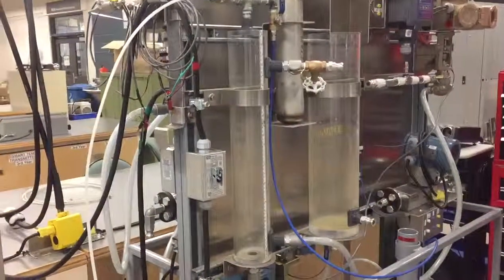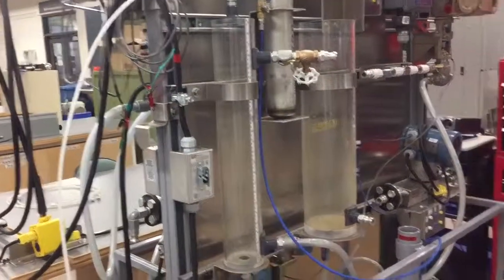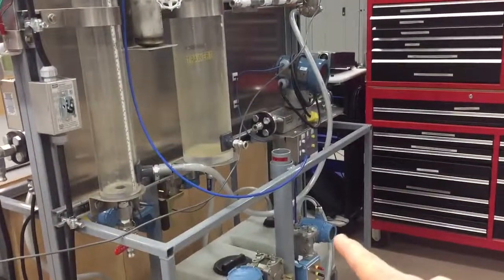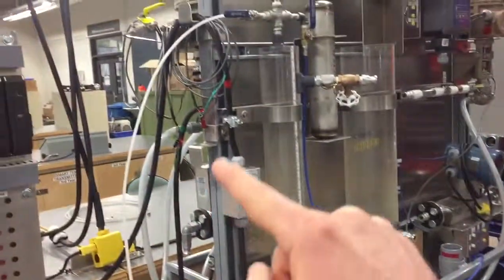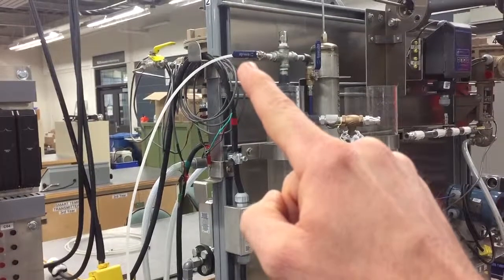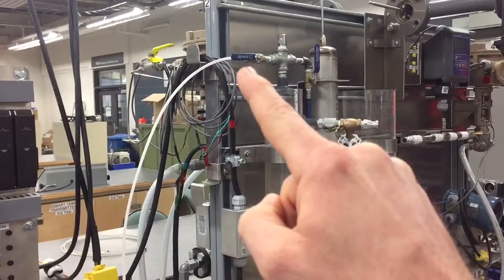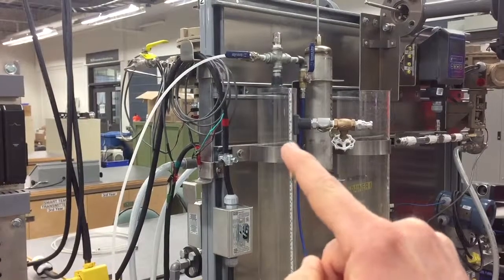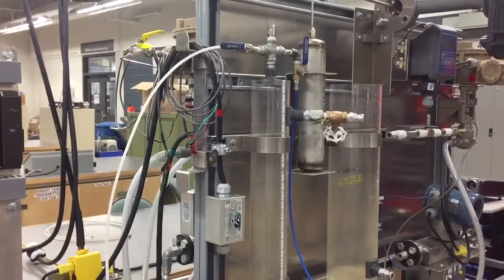The pressure is being controlled in this vessel right here. We've got a valve back here venting off gas. We've got a transmitter down here measuring the pressure, and then up here we've got a 5 psi instrument air supply coming in. We're attempting to control 1 psi in this vessel. It's been tuned properly around 1 psi.